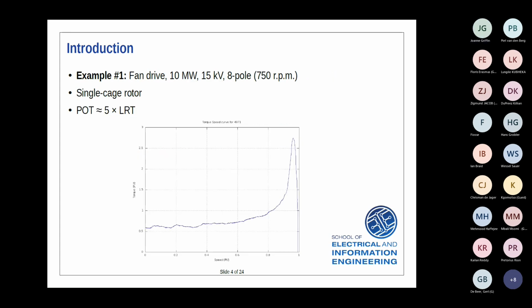All right, so this is an example from a test many years ago. It's a 10 megawatt machine, 750 RPM, single cage rotor, and you can see this absolutely classic torque speed curve. Very, very high pull-out torque - in fact 5 times the operating value. There's an operating value of about 0.6 per unit, and here it's peaking at about 2.8 or so. So very, very high pull-out torque - a classic single cage rotor design with very shallow bars.